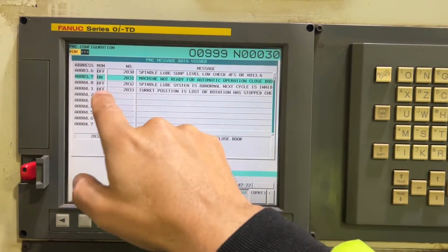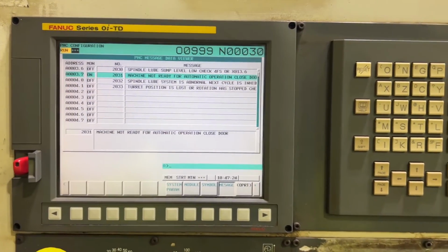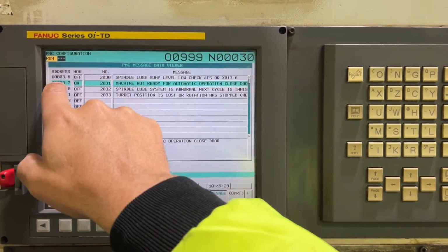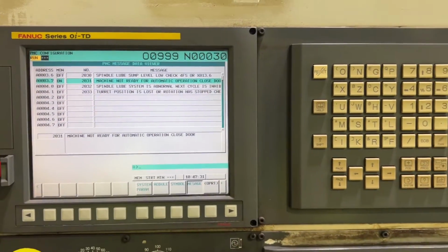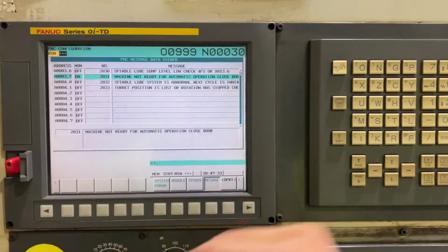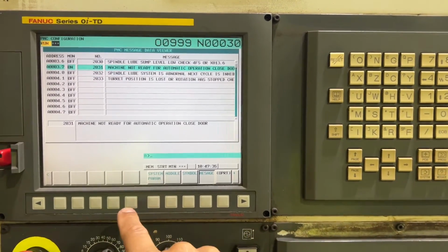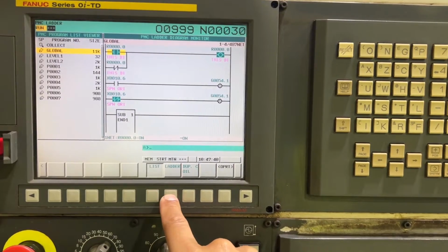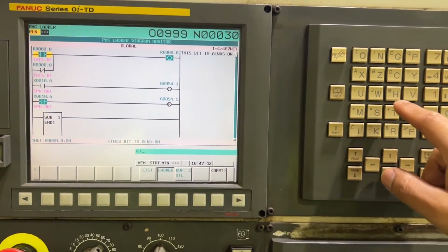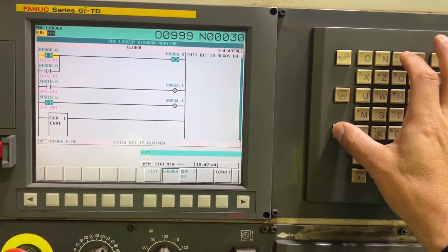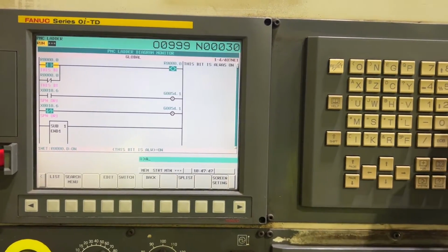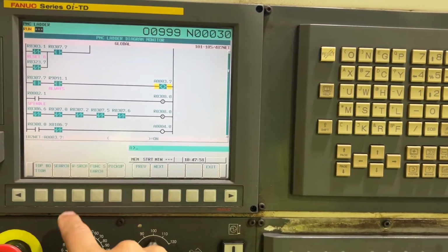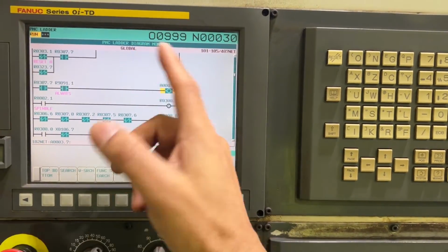You see that this is the coil on the logic. So we have to search for A3.7. Now it's on. So let's go back to the PMC ladder. We're going to select ladder and search for A3.7. Search and W search, it's right there.